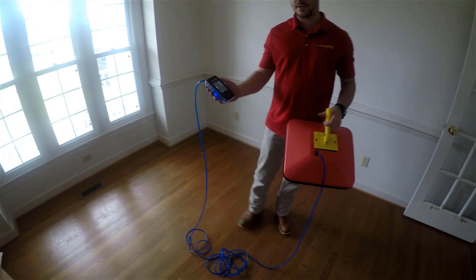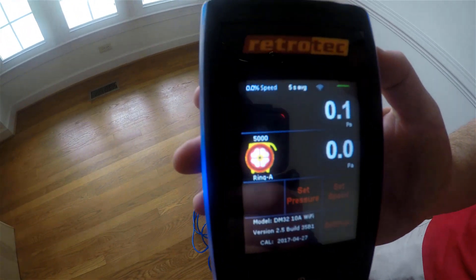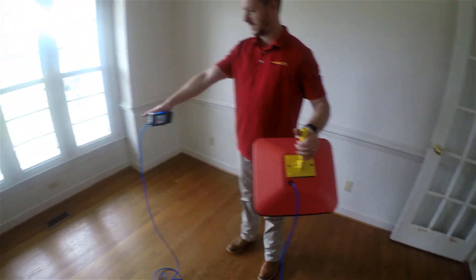In addition to smoke testing, using a pressure pan is also a great way to locate leaks. You would use this with the same DM32 gauge that comes with the blower door or Retrotec duct tester. In this scenario, we'll do the opposite of what we were doing earlier — this time we'll depressurize the house and pull air into the house through leaks in the enclosure. Here you can see I have my gauge hooked up to the blue port where the other end is attached to the pressure pan.